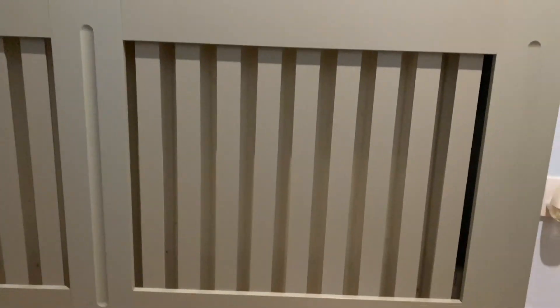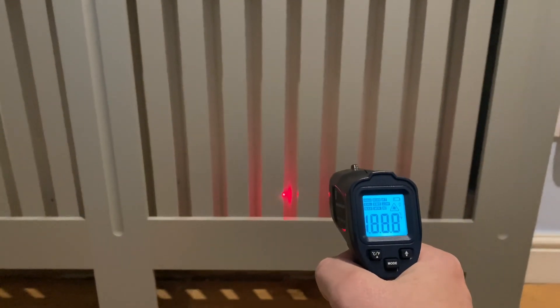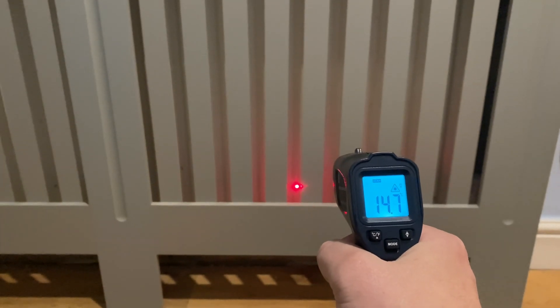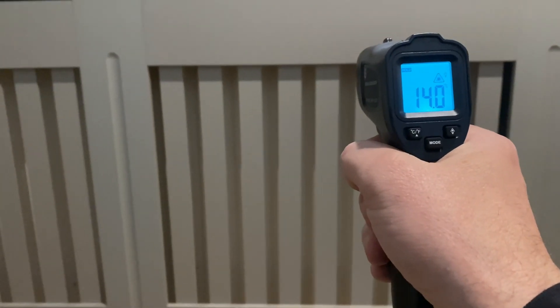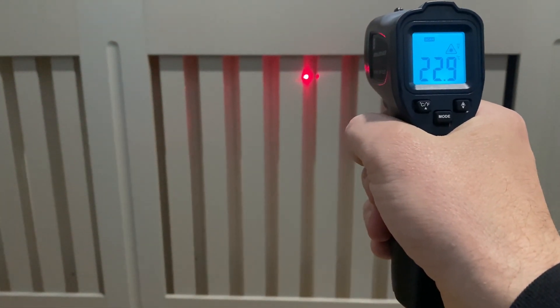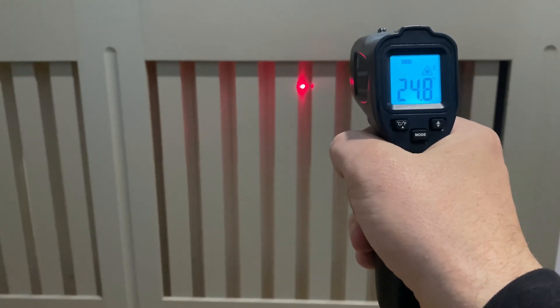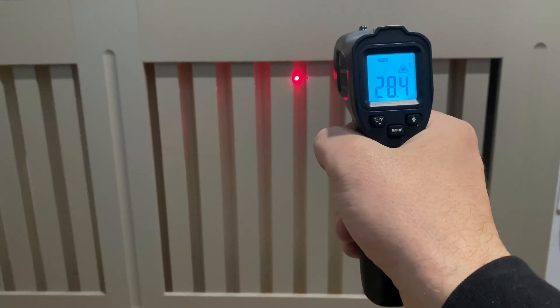This situation — the tool works out quite well because the radiator is in a cabinet. Reading: 14 at the bottom. I've just actually put this one on so I'll come back to it later. At the top: 22. You can tell it's just getting a flow supply to it — look how quickly that's increasing: 28.